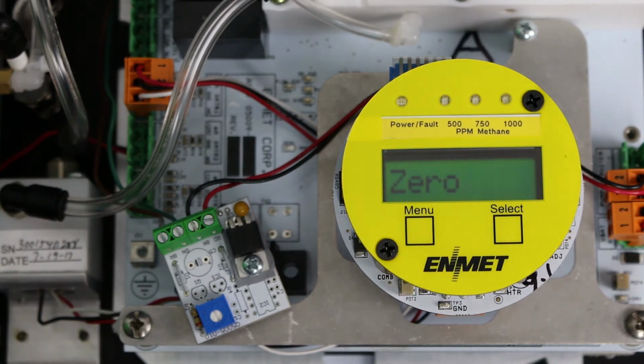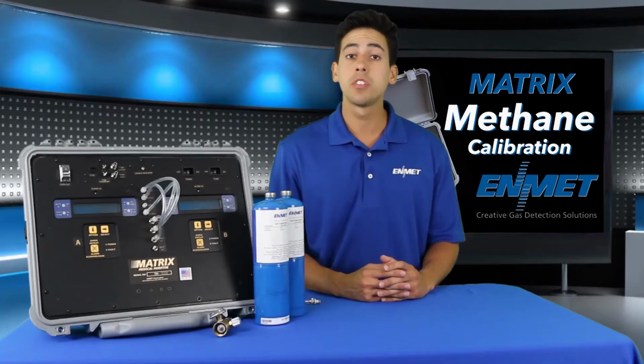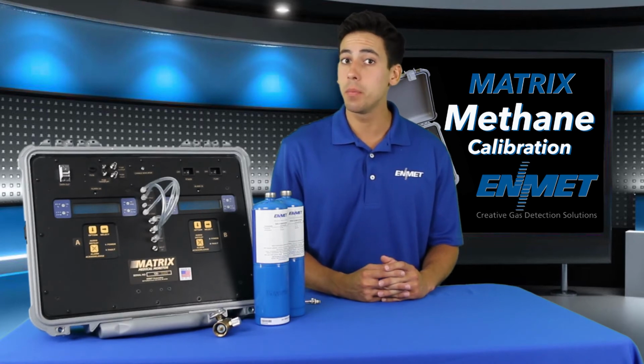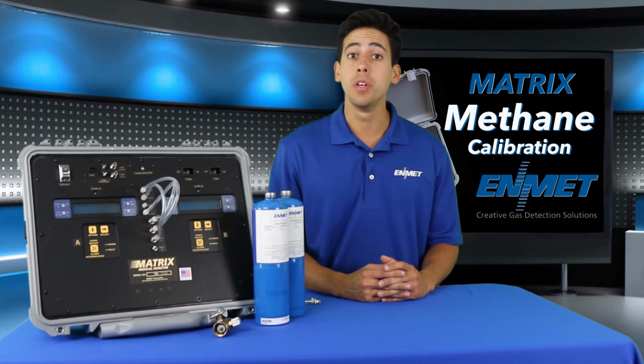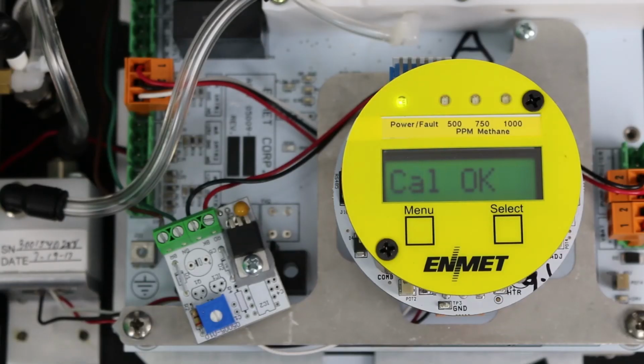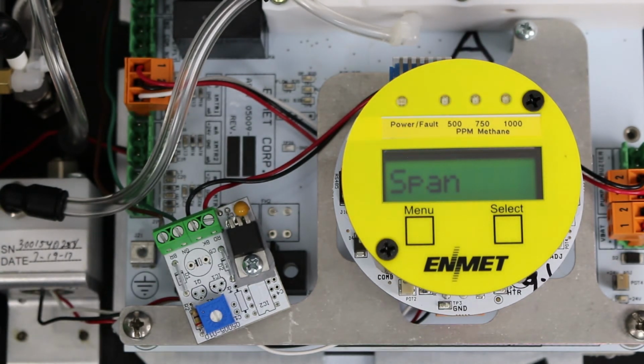The transmitter will monitor the sensor signal for stability for 30 seconds. If the sensor signal is stable after 30 seconds, the new 0 point will be accepted and cal OK will be displayed, indicating a successful zero. You will be returned to the maintenance menu with the span option highlighted.